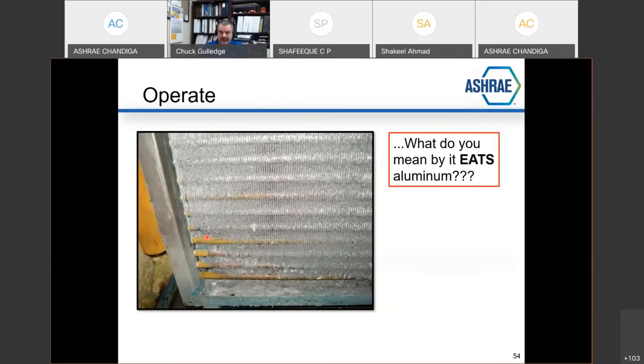So when it gets in the airstream, especially when somebody steps inside the air handler and sprays it on the coil, look what happens. Major disconnect between how this owner operated in response to the need and the engineering community not understanding a basic fundamental associated with these coils: they needed to have something different than classic copper tube and aluminum fin.